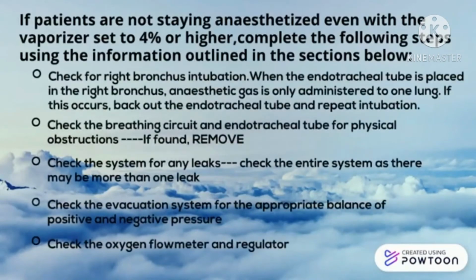Inspection shows the patient is not getting anesthesia even with the vaporizer set to 4% or higher. We can use the steps below to solve the problem. First, check for right bronchus intubation. Second, check the breathing circuit and endotracheal tube for physical obstruction. If found, remove.